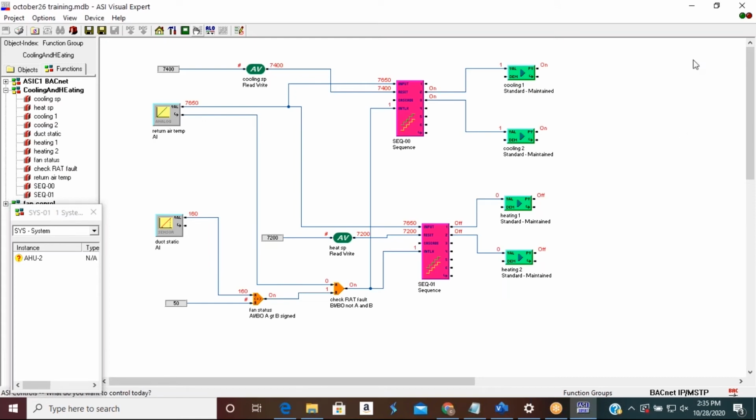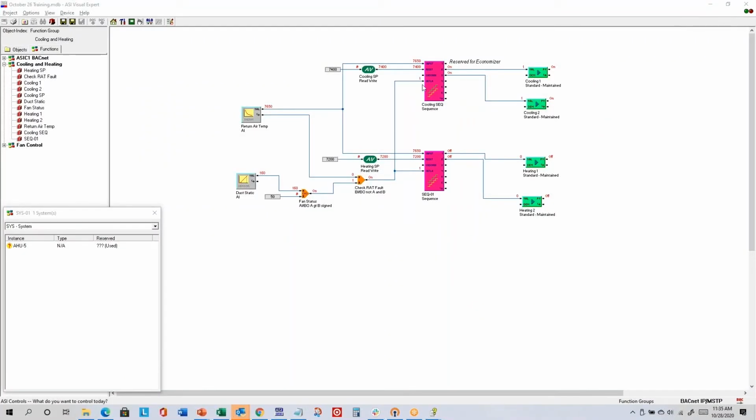Okay, I'll make myself the presenter again and share. And so if the interlock does ever drop out while the outputs are on, there's not a graceful shutdown. We don't honor the delayed stop times. It just shuts everything down. So if you did need to have a more graceful shutdown, there are delayed stop timers you could use external to the sequence that you could consider using.